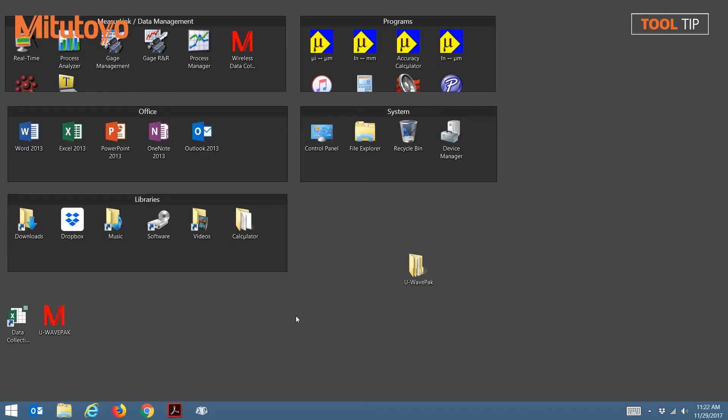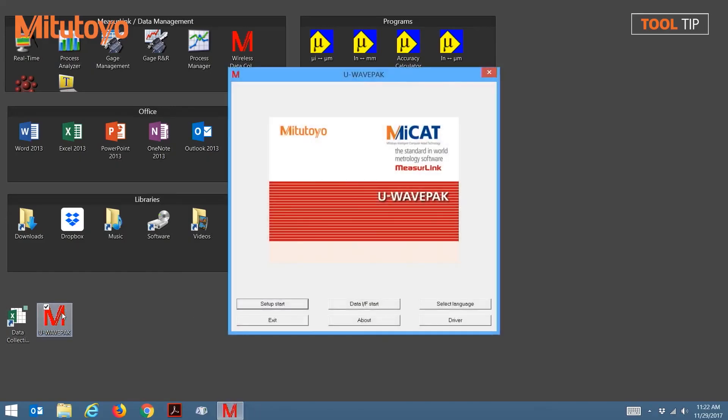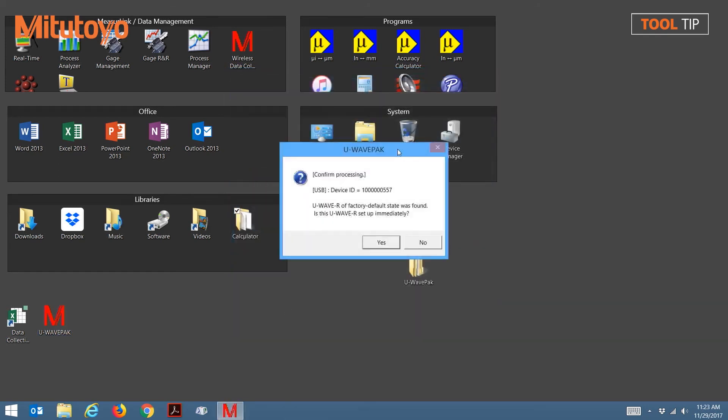Now we're ready to launch the U-WAVEPAK using the Desktop icon. To begin setting up the receiver, press the Setup Start button. If this is a brand new installation, this message box will appear to let you know that this receiver has not yet been initialized. To initialize the unit, press Yes.